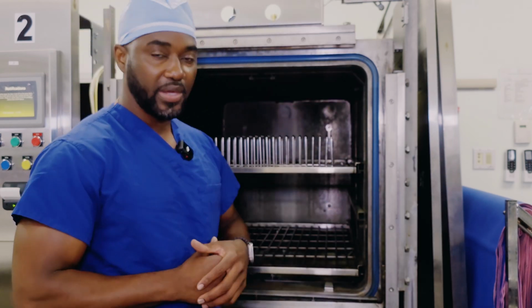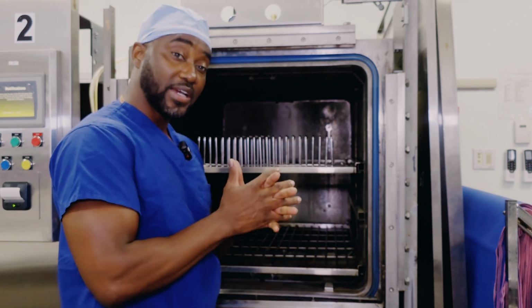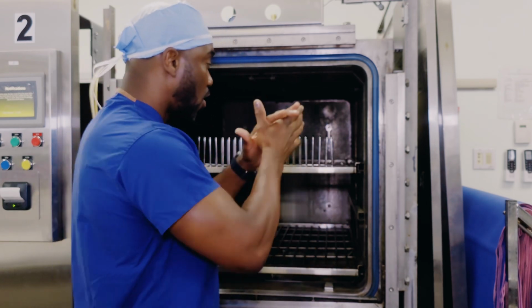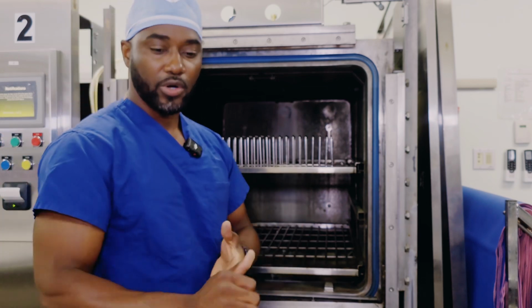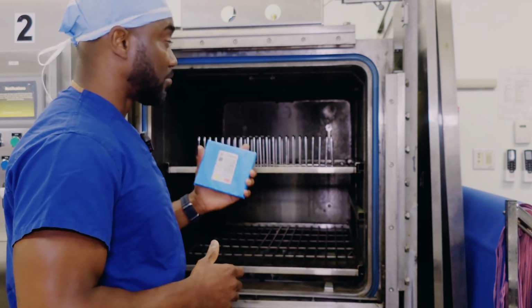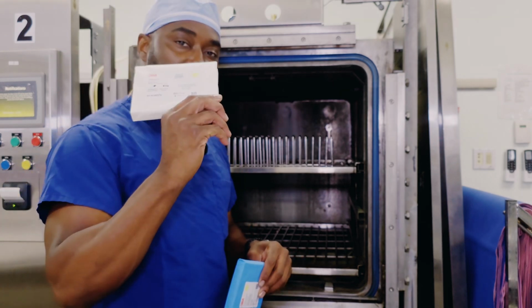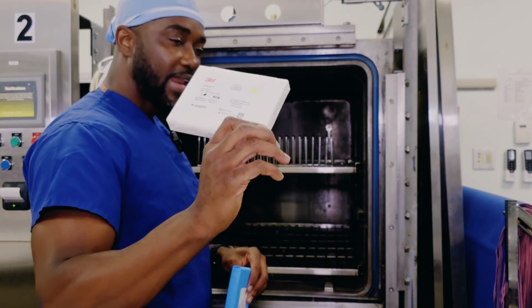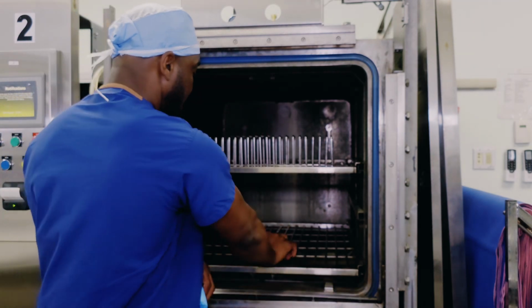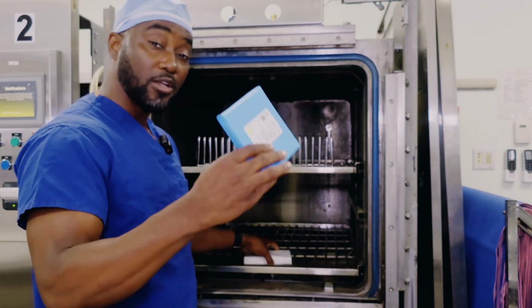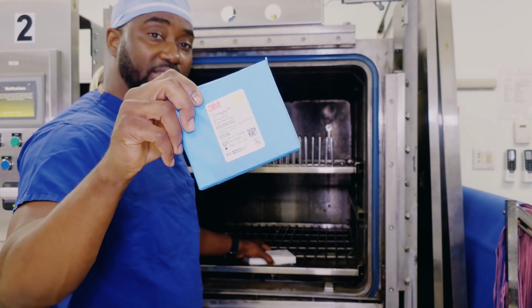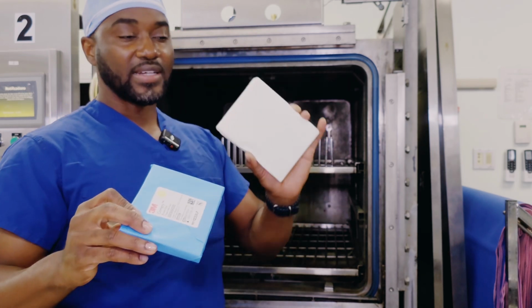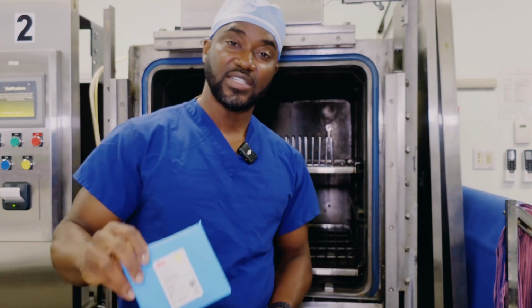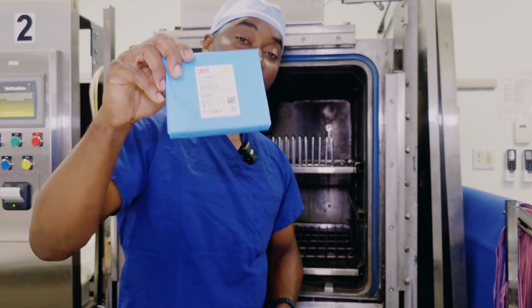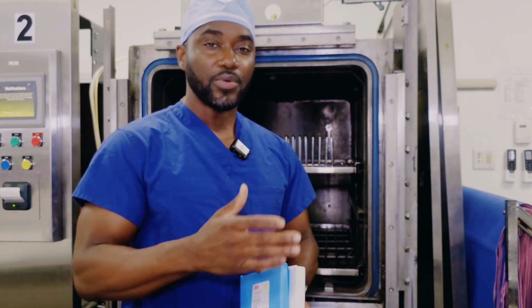When this has been repaired, pipings and everything, and put back together, we have to run a qualification test on our pre-vacuum sterilizer. How does that work? For your qualification test for this pre-vacuum sterilizer, we need to run 3 consecutive process challenge devices. That means we have to put a biological test in here and run an empty load 3 times, followed by 3 consecutive Bowie-Dick tests. And all of them should pass. Our biological test should pass in its 3 phases. Our Bowie-Dick test, which is the class 2 chemical indicator, should pass on the 3 trials. And after that, our autoclave is now qualified to run loads over the day.